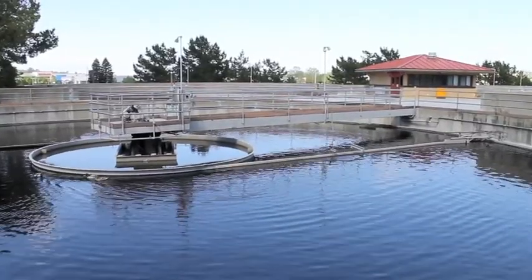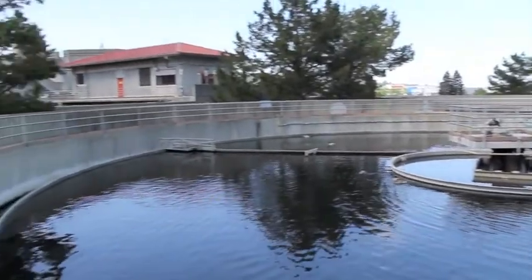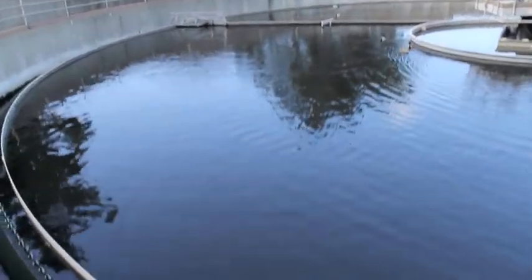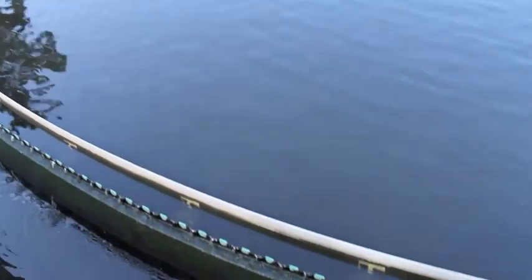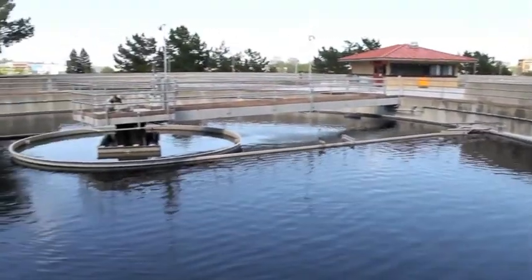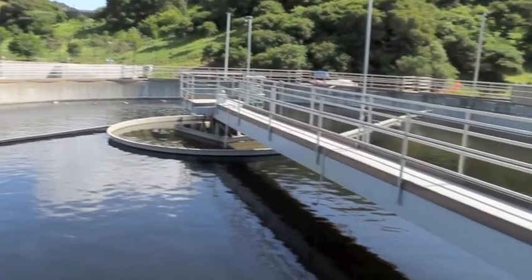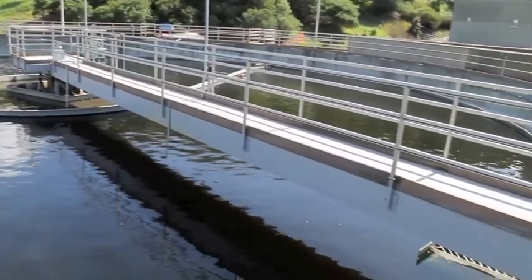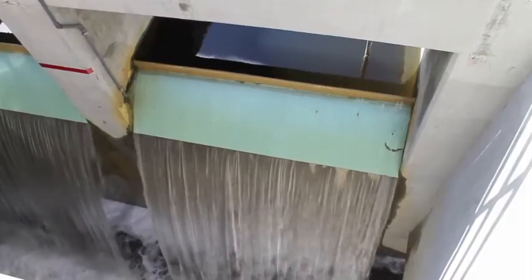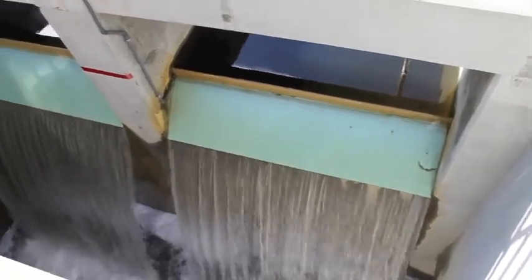When water enters the sewage treatment process, it can naturally be assumed to be contaminated with harmful bacteria, as is the nature of sewage. As such, it is essential to disinfect the water to remove potentially harmful bacteria that remain in it. In order to remove these harmful bacteria, the wastewater is disinfected with chlorine. Chlorine contact tanks release a computer-controlled dose of bleach to kill pathogens.